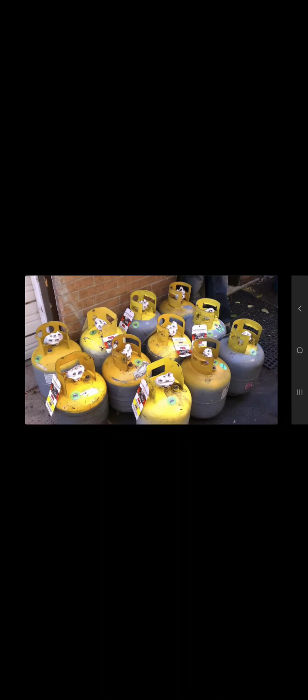You get guys like this, they don't have any type of gauge, any type of float. We got to weigh them. And there is a formula you use to weigh these. So I always tell people when you pick them up, do not get rid of that tag because we're going to use the back of that tag to monitor the weight of these guys. And we're going to get into that formula once we go through a couple more things. Okay, so yellow top, gray body may not be filled beyond 80% capacity.